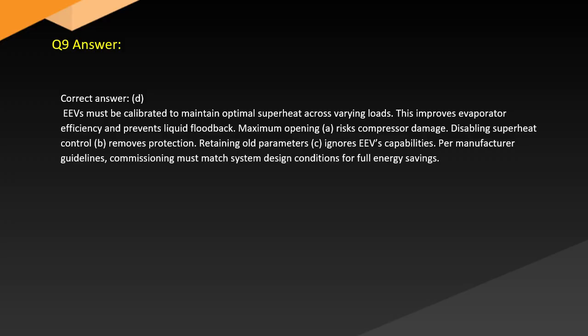Answer. Correct answer: D. EEVs must be calibrated to maintain optimal superheat across varying loads. This improves evaporator efficiency and prevents liquid floodback. Maximum opening (A) risks compressor damage. Disabling superheat control (B) removes protection. Retaining old parameters (C) ignores EEV's capabilities. Per manufacturer guidelines, commissioning must match system design conditions for full energy savings.